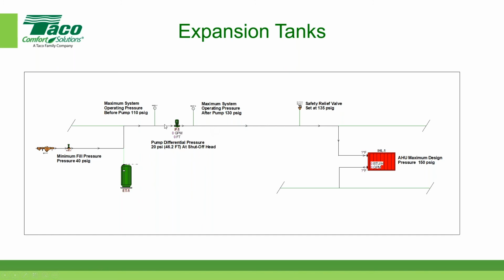As the pump pressure differential increases, the discharge pressure remains constant because that's where it's connected to the expansion tank, but the suction pressure begins to drop. If the suction pressure drops low enough, you could have the pump cavitating. So one of the main responsibilities of the expansion tank is to ensure that you have a fixed minimum pressure at the pump suction in order to prevent the pump from cavitating. So hopefully that answered that question, Brett. Yep, that was a great answer.